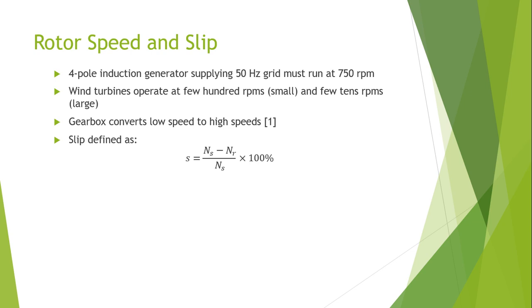The value of slip at full load varies from 6% in the case of smaller motors to 2% in larger motors, and usually it is taken as 3% for calculation purposes. The induction motor never runs at synchronous speed. The speed of the motor is always less than the synchronous speed.